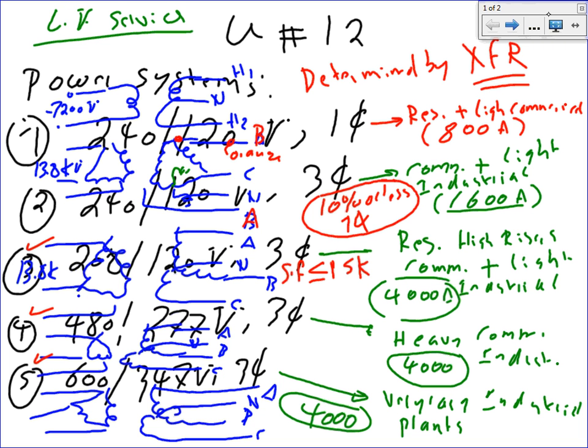Any questions guys about number 3? A 3-phase service, perfect for non-residential. The last one is 4. This is the most common for heavy commercial and industrial. A 480/277 system, and on the primary side it is still 13.8. Heavy commercial and industrial, big buildings. When I say heavy commercial here, I mean larger than 15K square feet. Again, rule of thumb. If you go down and talk to the guys you work with and say Chad said this, they might say, where did he get that number from? I hope you understand, it's a rule of thumb, how I see it.